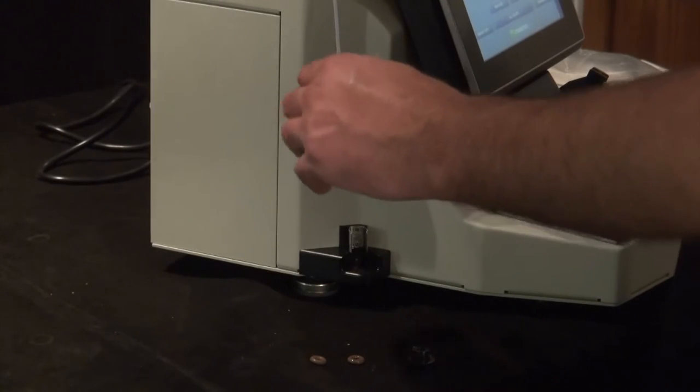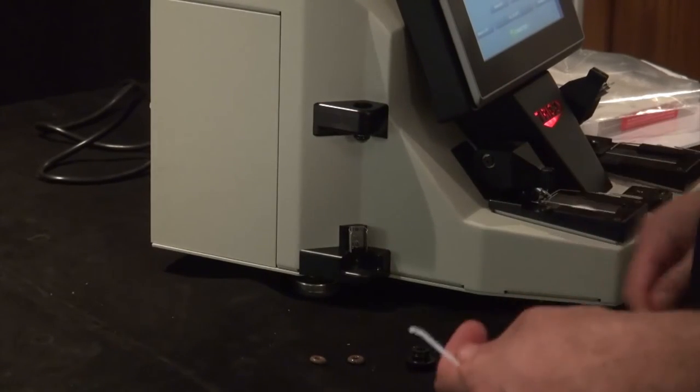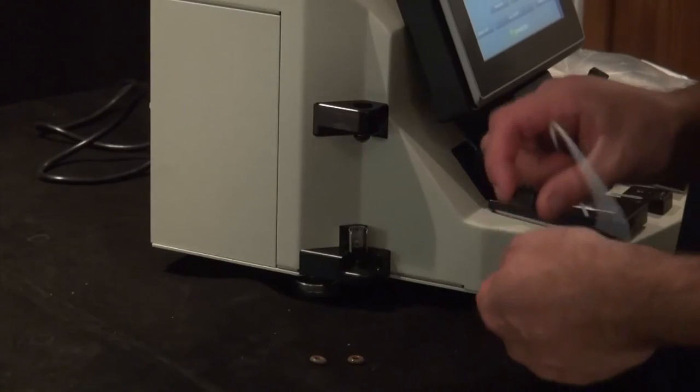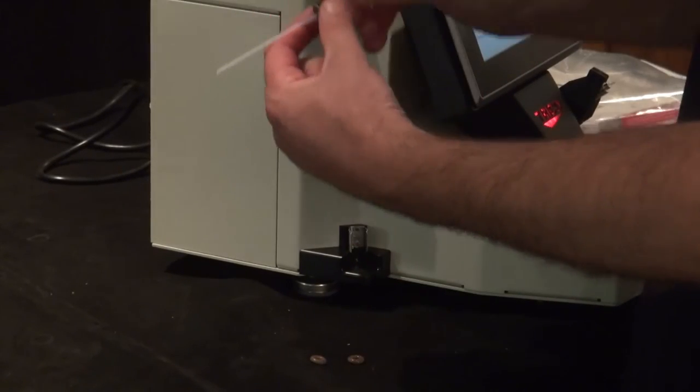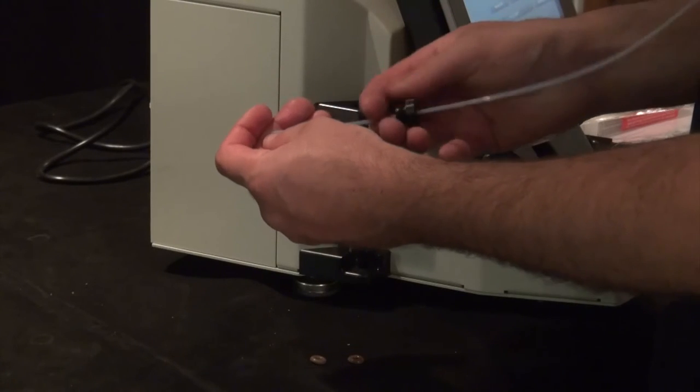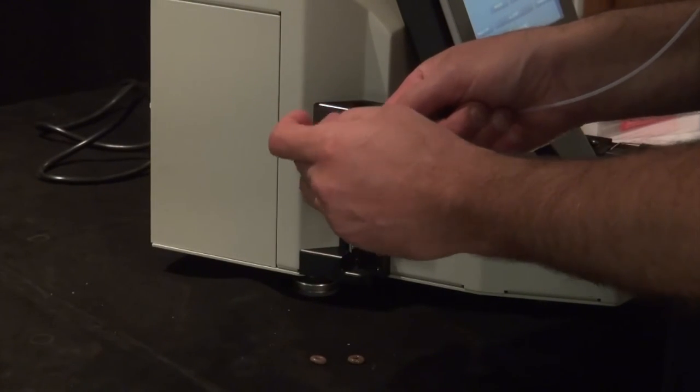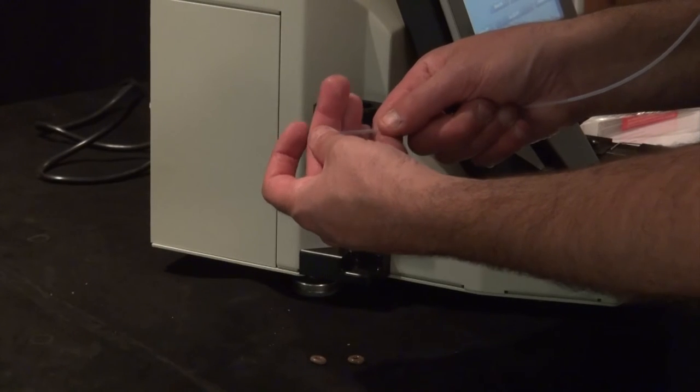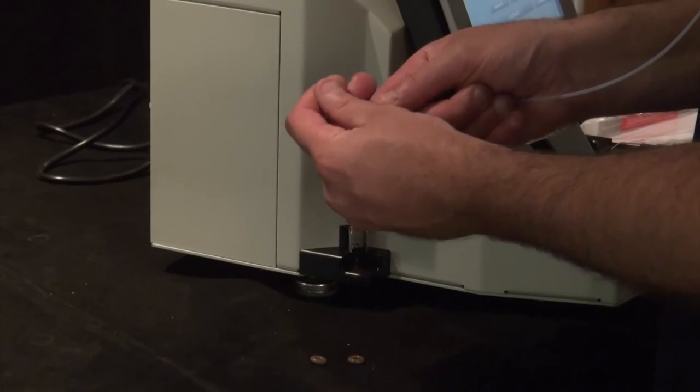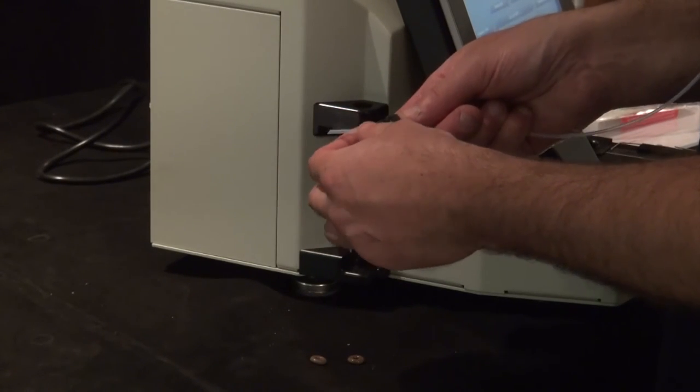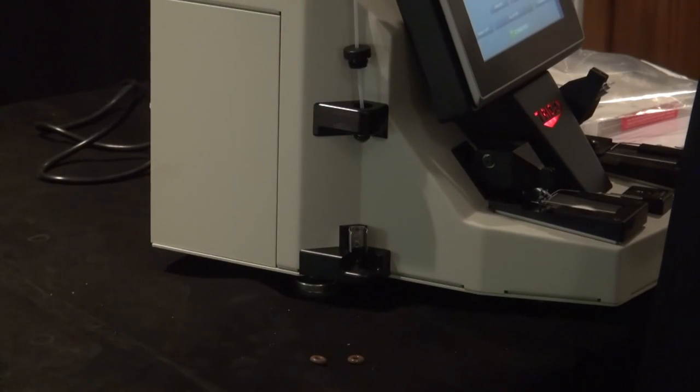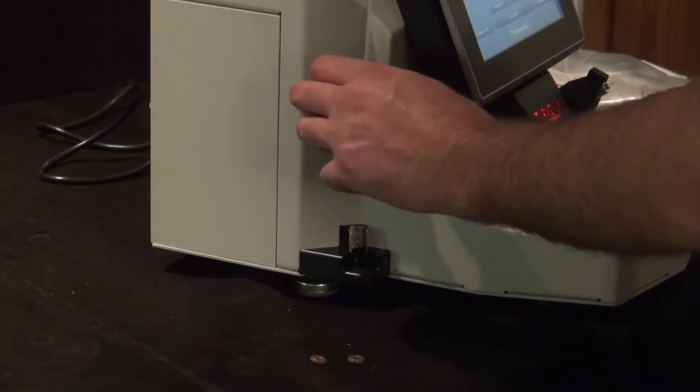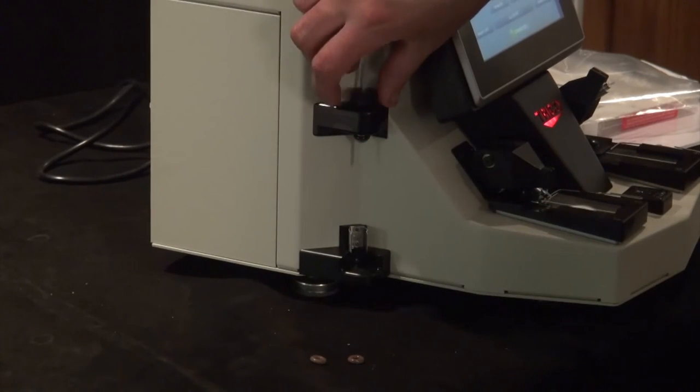If you want to replace it, the easiest way to do that is to take your sample tube and put it through the top cap, then take your o-ring and put it on the end to keep it in place so it's not moving around when you put it in. Then all you have to do is insert the tube in and tighten it down.